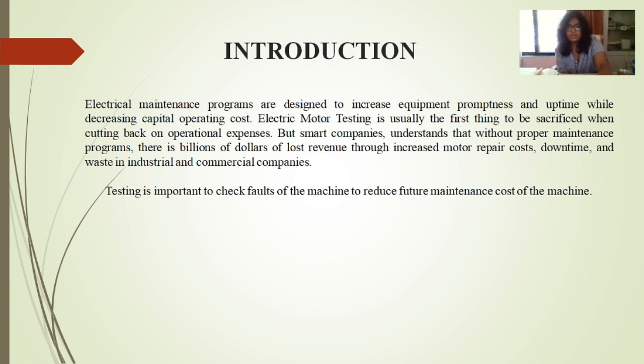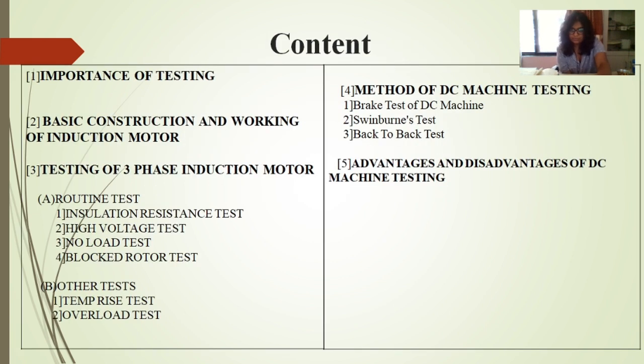Electrical maintenance programs are designed to increase equipment promptness and uptime while decreasing capital and operating cost. Electric motor testing is usually the first thing to be sacrificed when cutting back on operational expenses. But smart companies understand that without proper maintenance programs, there is billions of dollars of lost revenue through increased motor repairs, downtime, and waste in industrial and commercial companies. Testing is important to check faults of the machine and to reduce the maintenance cost of the machine.